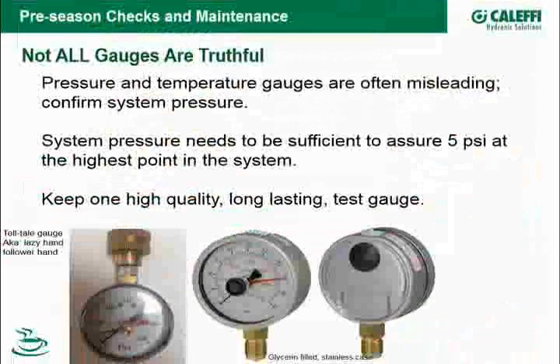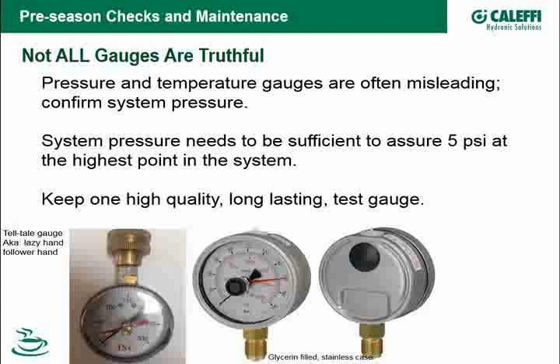Gauges. Probably my biggest pet peeve of all the years I've worked on equipment is the gauge that comes with a lot of the boilers, the tridicator gauges they call them, where they read not only pressure in the boiler, but they'll tell you the temperature in the boiler. Some of them will have a little dial in there that gives you the altitude of the fill water, hence the name tridicator for 3 different functions. They're not always the best quality. I would advise you to get a good quality gauge, and it's worth spending a little extra money on that.